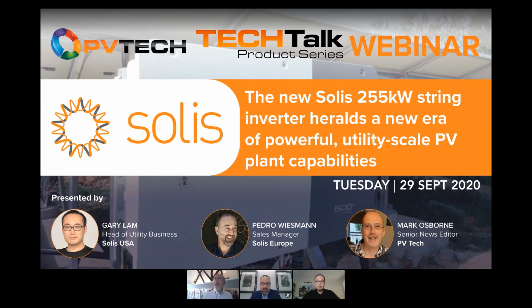Yeah, just one final related to this. So how many inverters can work in parallel? Currently, I think the system would work up to 50 or more. But right now the largest solution we're deploying is about 6.3 megawatts, and it hardly reaches that. And that should be plenty for us. The limitation on the inverter is mainly on the communication side, how much our communication supports. But that isn't affected by the power, AC output, or harmonics, anything like this.